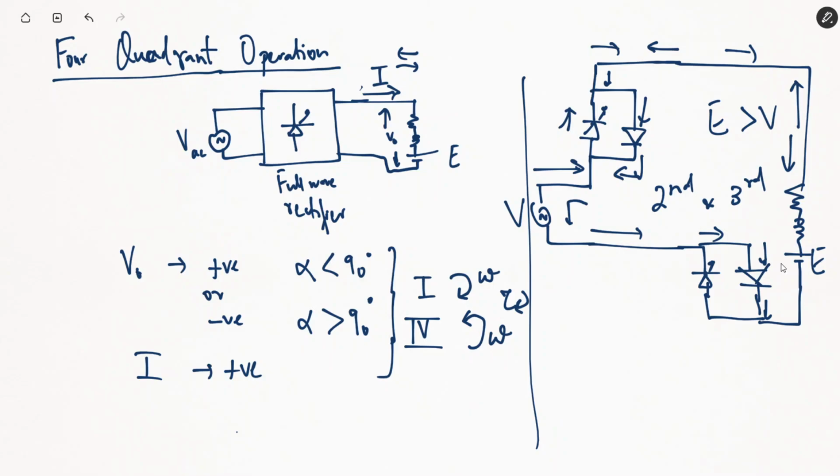and we are providing an arrangement for bidirectional flow of current through diodes by placing the diodes in parallel with the thyristors, but in an opposite direction, we can let the current flow to the source. This will actually let us capture the energy while braking the system, while making sure that we want to actually reduce the speed of the system. We can capture the energy and let it flow back into the source.